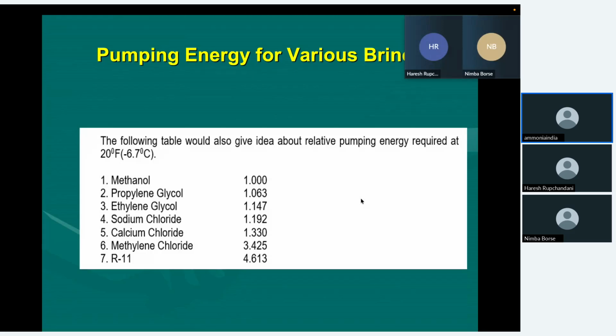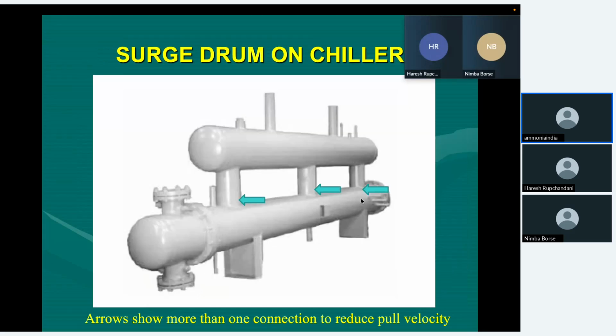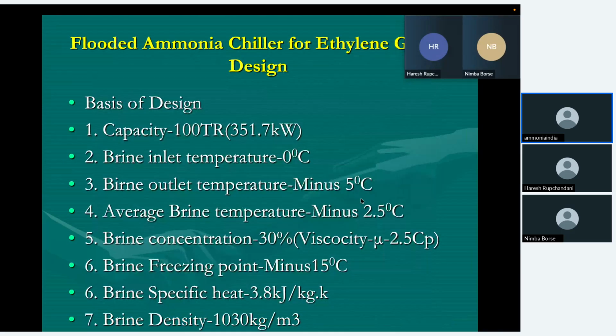We must always ask why we are doing this. What is the reason behind it? What must we do to avoid problems? Then there will be no problem. I have designed nearly, as Anand Saab has said, nearly 700 plants, but nowhere have I faced any problem so far. So this surge drum on the chiller, these pipes, which are very important, the arrow shows more than one connection to reduce the pull velocity. Now let us design one ammonia flooded chiller.